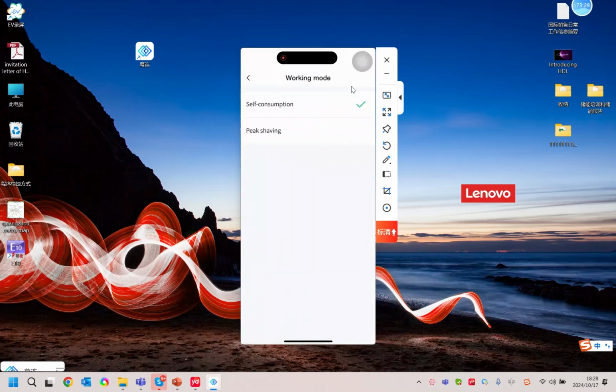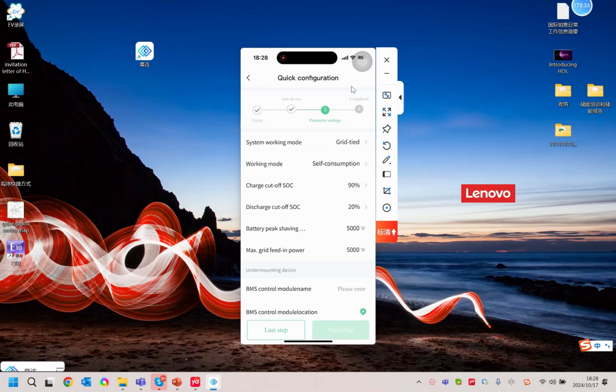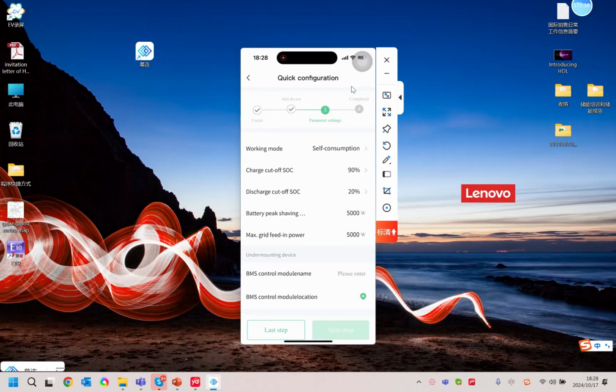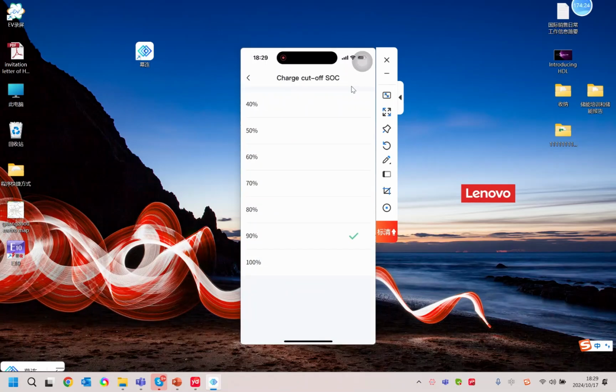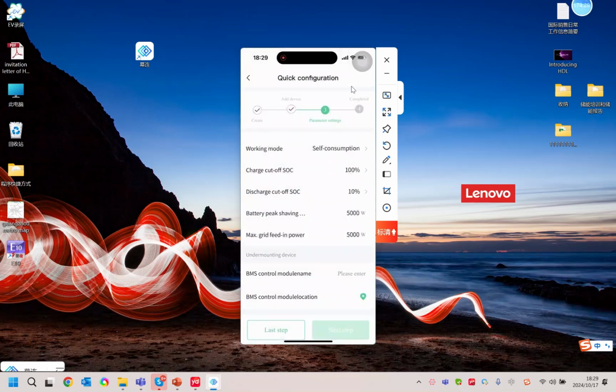And the working mode here, we choose self-consumption. The next parameter, charge cutoff SOC - this is the question already asked, that in order to protect the lifespan of the battery, you need to set the maximum charge capacity. We recommend 90%, and also the lowest discharge level of the battery, better to set like 20%. Of course, you can set to 10%. And for the charging cutoff SOC limitation, you can also choose 100, but it's better to choose like 90%, not fully charged.